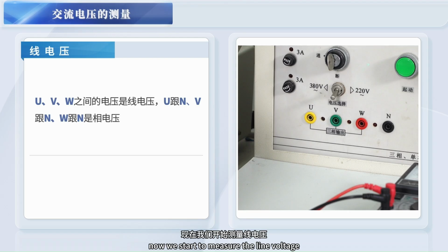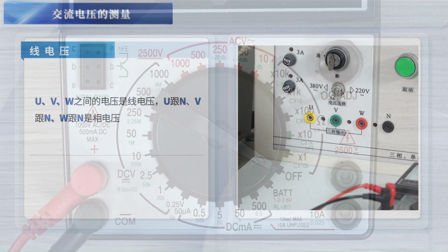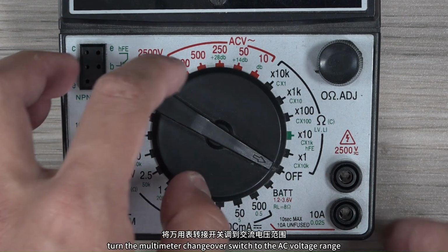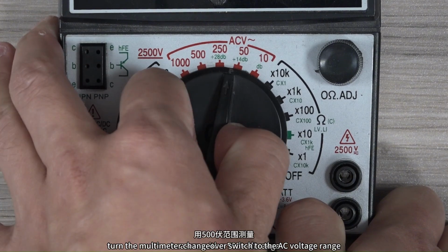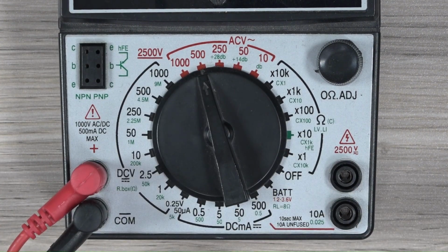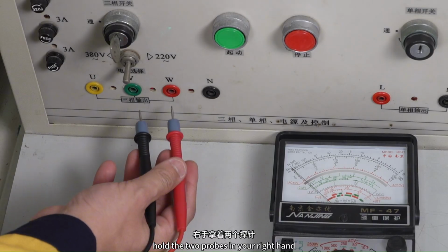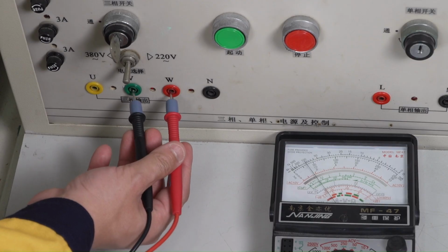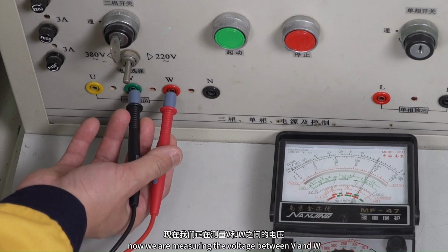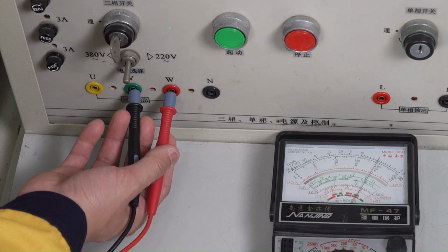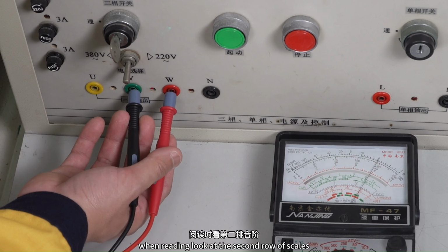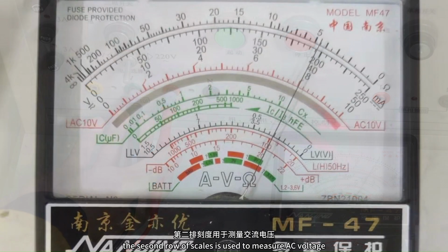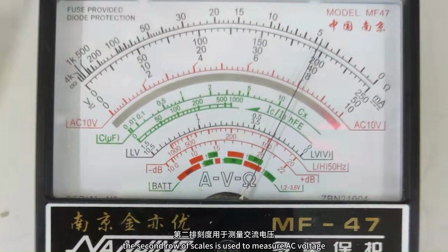Now we start to measure the line voltage. Turn the multimeter changeover switch to the AC voltage range. Measure with the 500 volt range. Hold the two probes in your right hand. Now we are measuring the voltage between V and W. When reading, look at the second row of scales. The second row of scales is used to measure AC voltage.